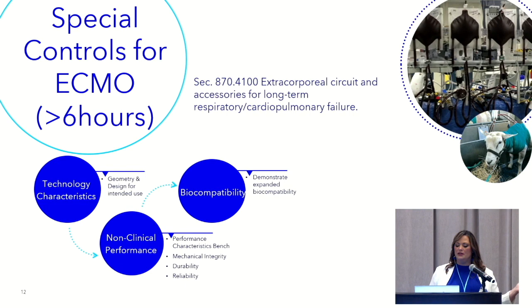The next piece is, once you determine those characteristics for the intended use, we have to look at bench testing. So does it have mechanical integrity, durability, reliability? And again, this is for the intended use. When we bring you products for cardiopulmonary bypass, we're going to test those for the 6 hours and make sure that they're really reliable and provide the best possible options for that short term. For this long-term indication, the same thing happens, but we're going to test it for long-term, right? We're going to test it for 14 days, 30 days. We're going to look at that longer-term testing. Then there's testing for biocompatibility. Again, they're going to look at extended-use biocompatibility. So all of these things are for what each of the clinicians are seeing for ECMO. Again, ECMO duration was averaging 7 to 14 days prior to COVID with cardiac or respiratory patients. Now they're getting a little bit longer.